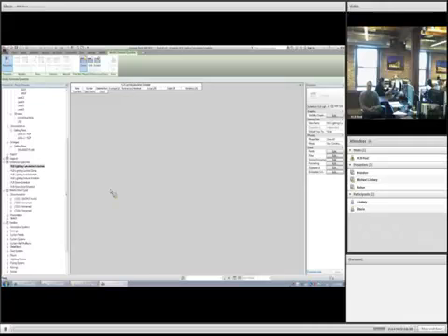Oh, you do a summary for your LPDs? In essence, there's two ways of going about it. One is a whole building method, where you call the entire building whatever it is, and there you go. We rarely use that. Usually what we use is the space by space method. Okay, cool. That's what this is set up for.